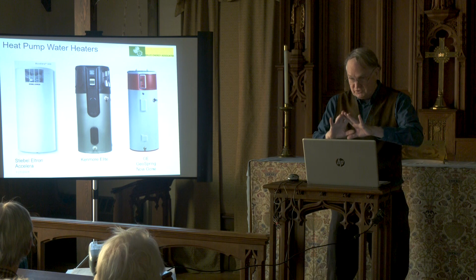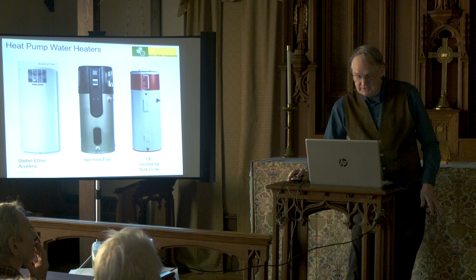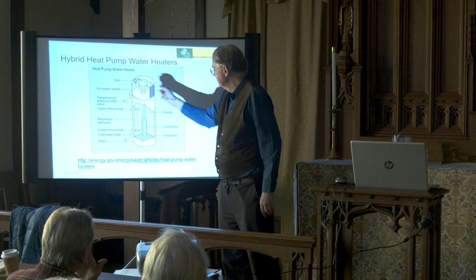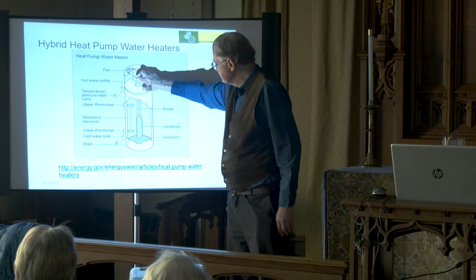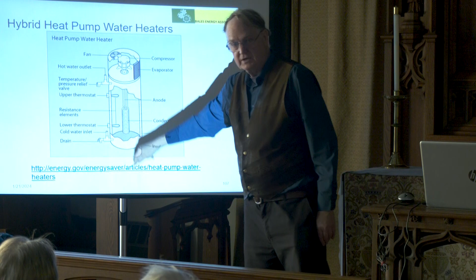What's the limitation on existing construction for air-to-water? It doesn't make hot enough water. You can't put it on your baseboard, because baseboards are designed for 180 degree water, and this puts out 120 degree water. If you have a radiant floor, you can heat a house with 120 degree water, but if you have radiators, you can't. If you have panel radiators on the walls, you might be able to heat with 140 degree water, or even 100 if you've super insulated your house—you could almost heat it with a candle. Anyway, let me plow ahead and show you how this works: the air blows through here, the energy gets taken out in this coil, and then it transfers down into the water.